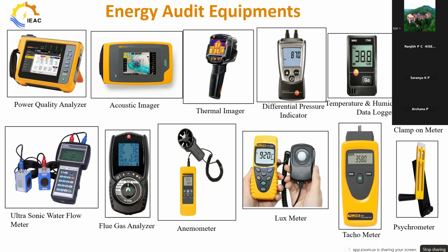From day 1 to the next day, 24 hours. Normally it has to be operated for 24 hours. We connect at the 11 kV line, or at the 440 volt line, and it will be connected for 24 hours of the day, and we will analyze the data for 24 hours for their load variations, demand variations, power factor variations, the harmonic spectrum, and harmonic analysis. That has to be done with the power quality analyzer.